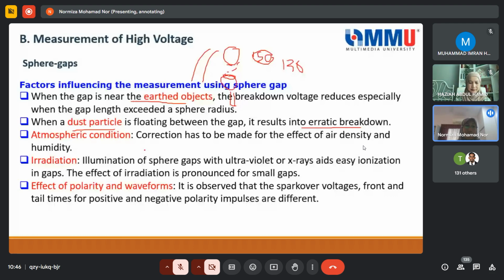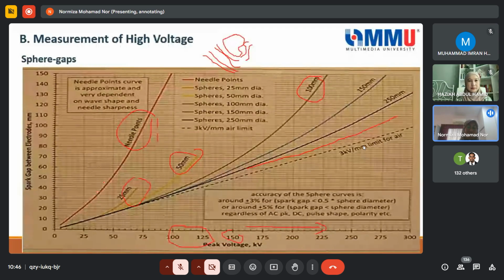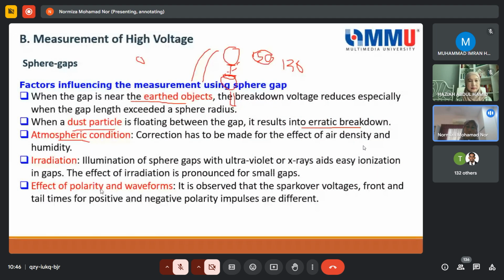Okay, so another is the dust particle and atmospheric condition. This one we know that we have to correct according to the standard. And then irradiation, where illumination of the sphere gap is used. There are some techniques, such as ultraviolet or X-ray aids, which allow the breakdown to happen directly from one end to the other. The effect of irradiation is pronounced for small gaps. If you have a very small gap, it is very much affected by this irradiation technique, which is used to aid the breakdown from the live conductor to the earth conductor. And then another is the effect of polarity and waveform.